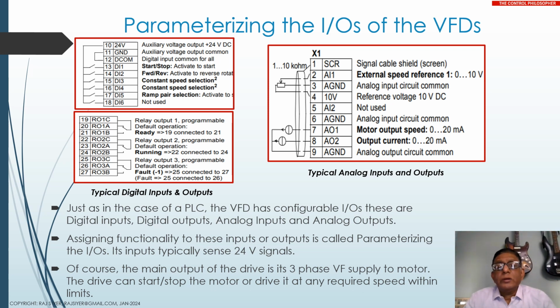And on the right side, you have analog inputs and outputs. There are usually two analog inputs. The first analog input takes in 0 to 10 volts, and that 10 volts is also coming from within the VFD. So all you do is connect a potentiometer as shown. You should connect a potentiometer that is higher than 1 kilo. Don't connect a low value potentiometer, don't connect 100 ohm, 500 ohm and all. It has to be typically about 5 kilo, otherwise that 10 volt supply will get overloaded.